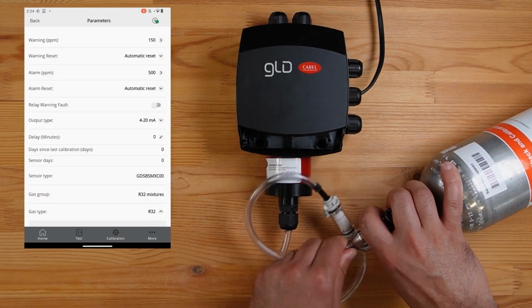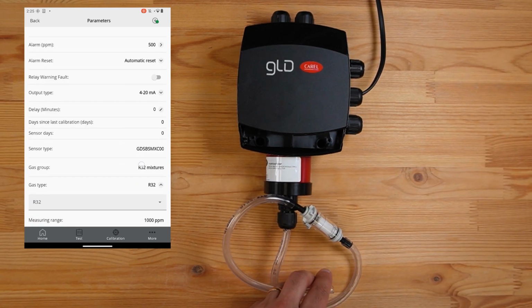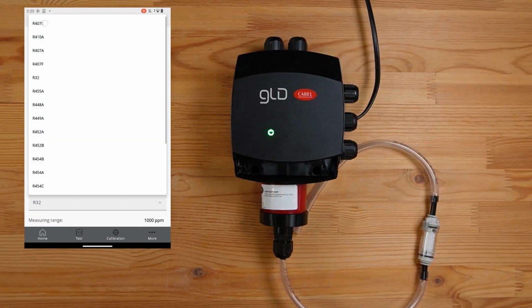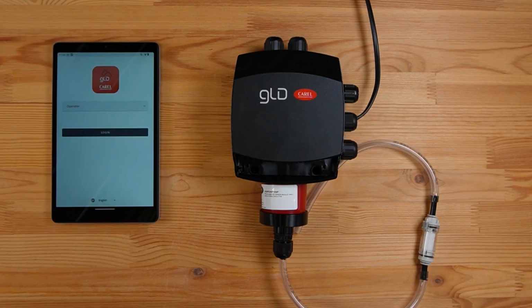Ensure you go back to Parameters to change the gas type from the test gas to the gas the unit is supposed to measure. Correct completion of the calibration process can be verified by checking that the value of days since last calibration has been updated to 0. Disconnect the app from the unit. Finally, make sure the gas detector is no longer in service mode.